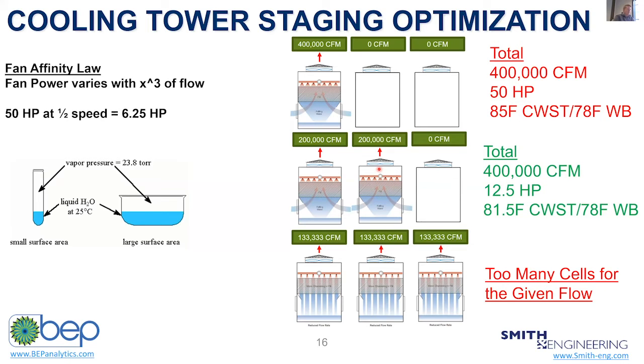So the simple optimization answer here is run as many towers as you can before you start getting uneven flow distribution through the fill. And from our empirical data, you see the channeling here, the theoretical. Think about that sprinkler in the cooling tower. It doesn't have enough pressure because I'm spreading the flow out too much, so it's not spraying and fully wetting the fill. So the theoretical evidence says that there's less pressure drop where the water is not, and the air is going to pass through there and not pass where the water is. I get ineffective heat transfer.